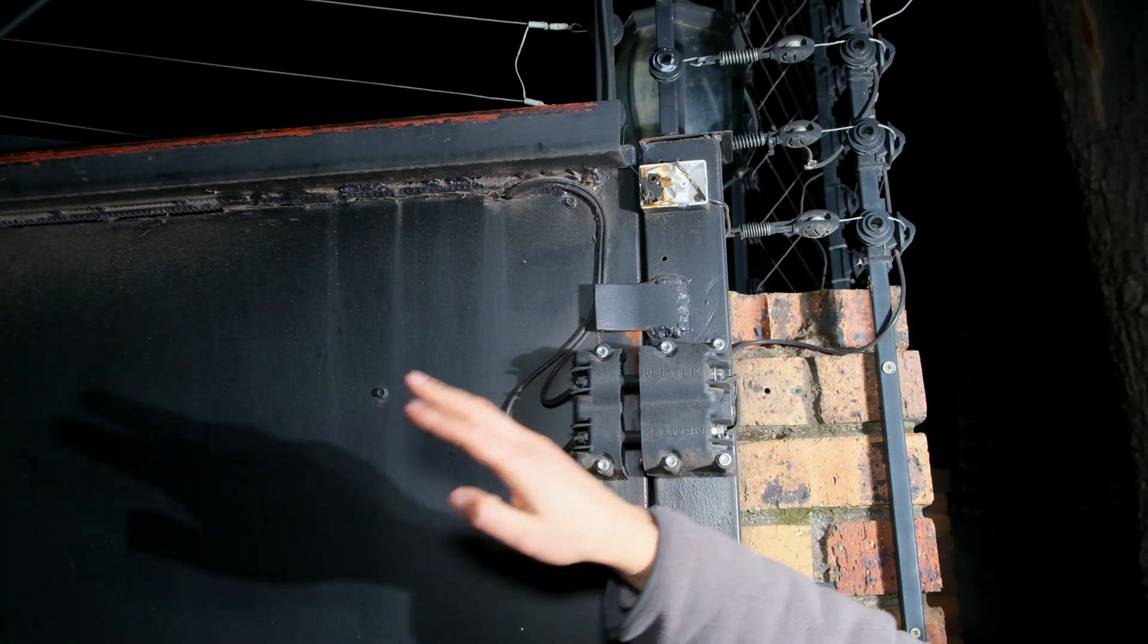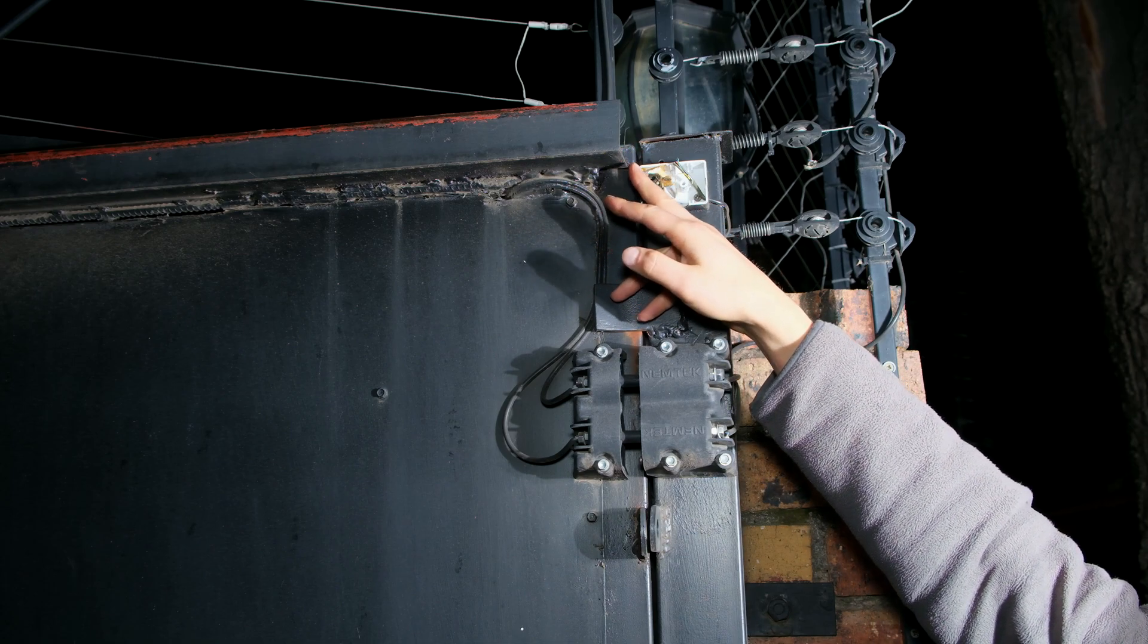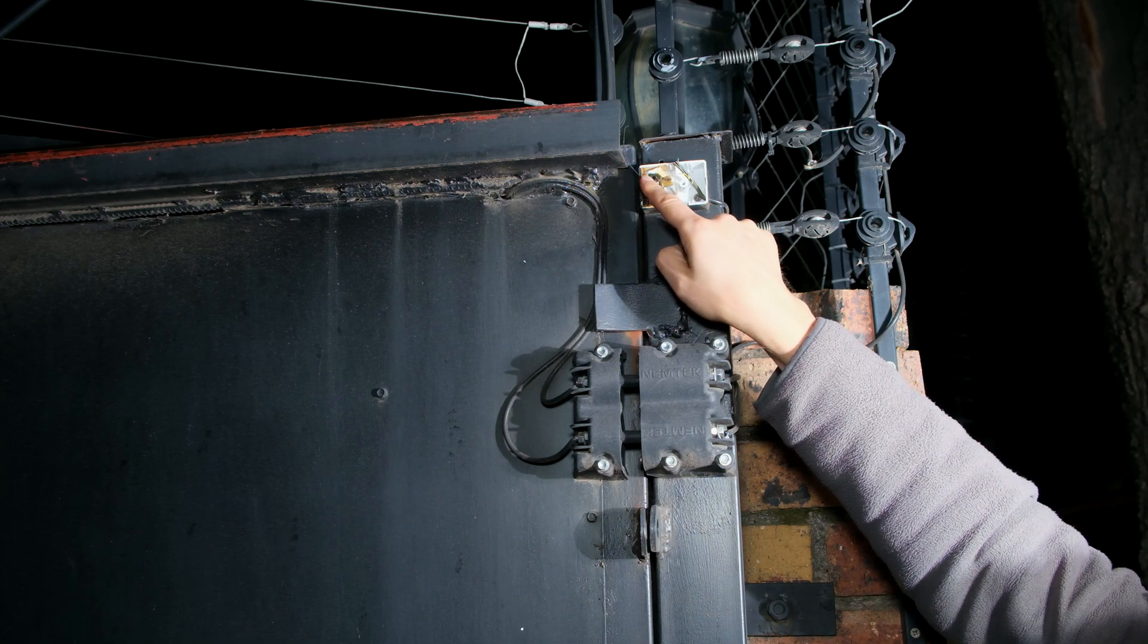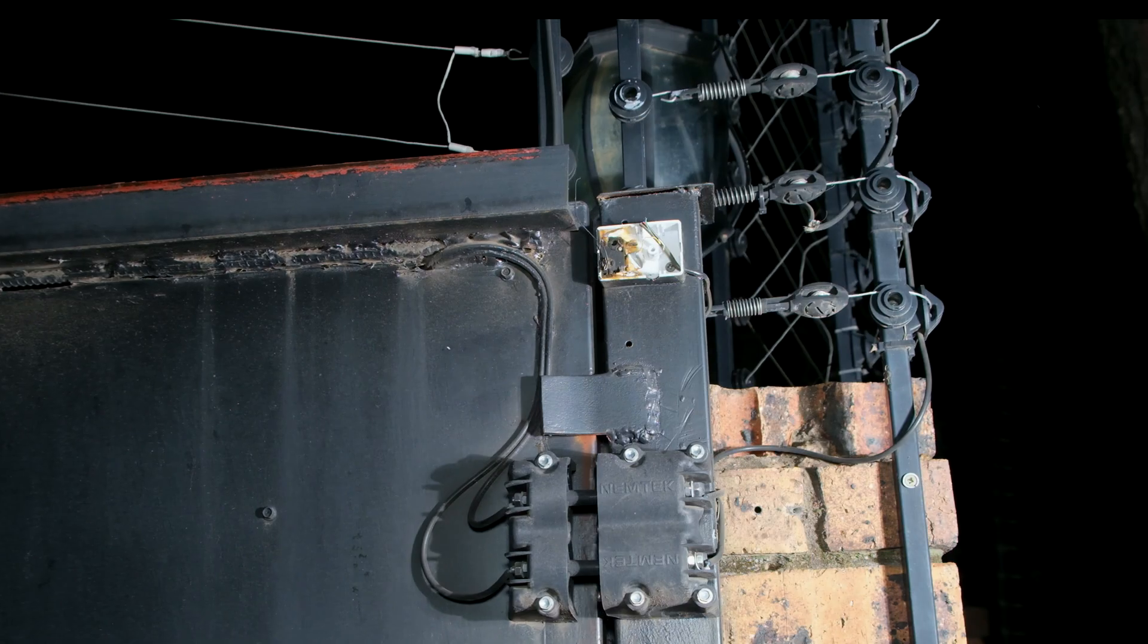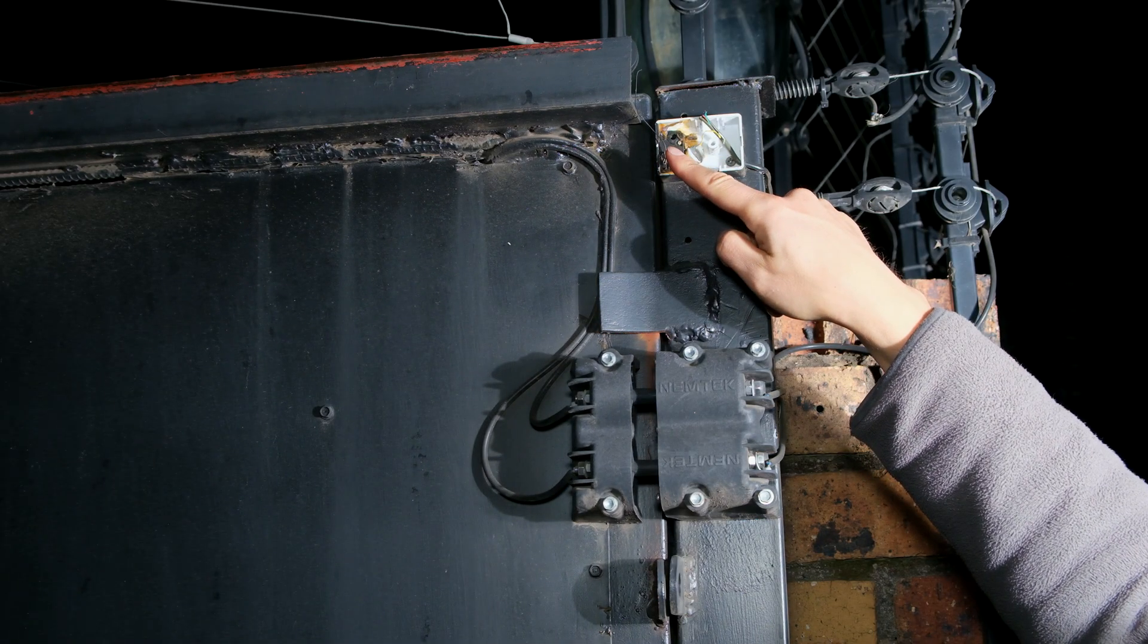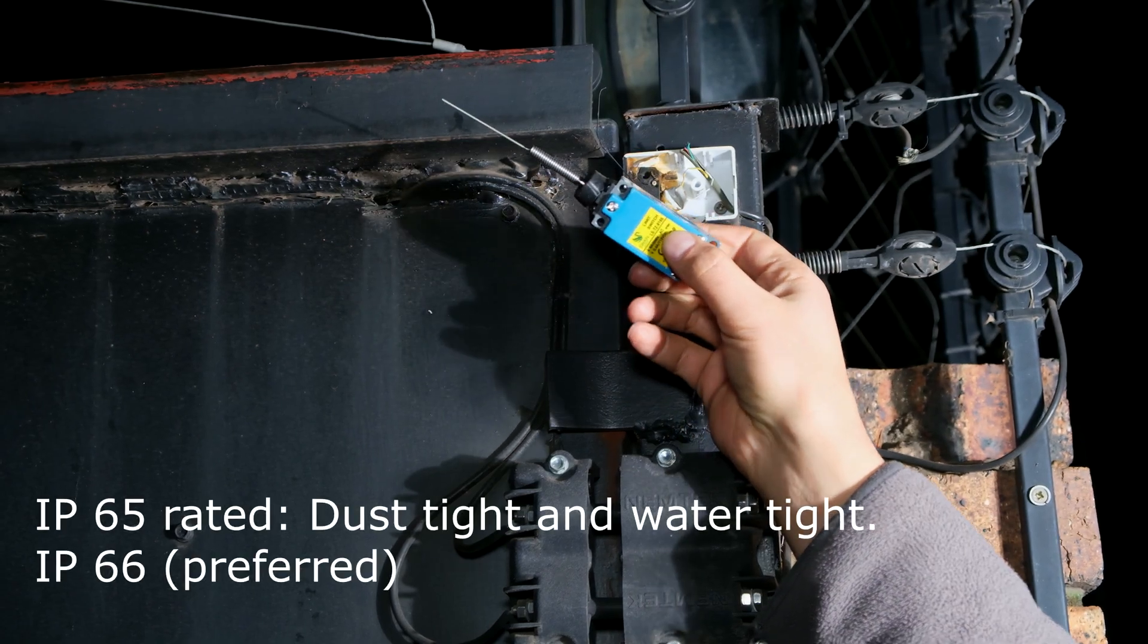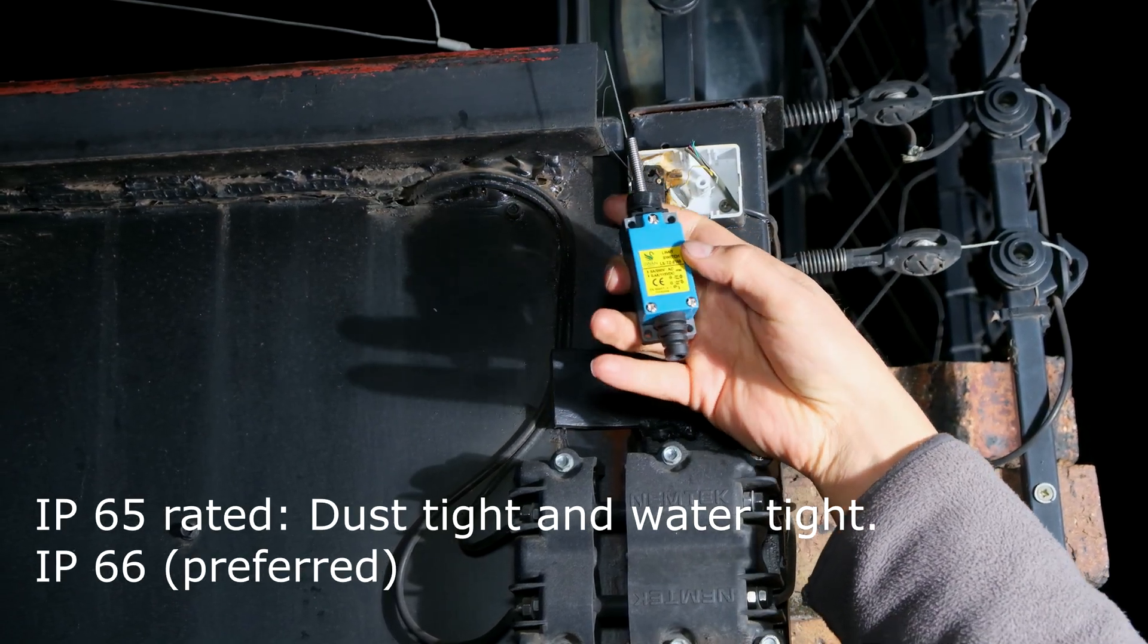Over here I have a gate, and I can determine if the gate is open or closed by using a limit switch. At the moment there is a limit switch here, and when the gate is opened that metal pushes the limit switch into the closed position. This can also be connected to your alarm system, but preferably you'd want an IP-rated industrial type limit switch.